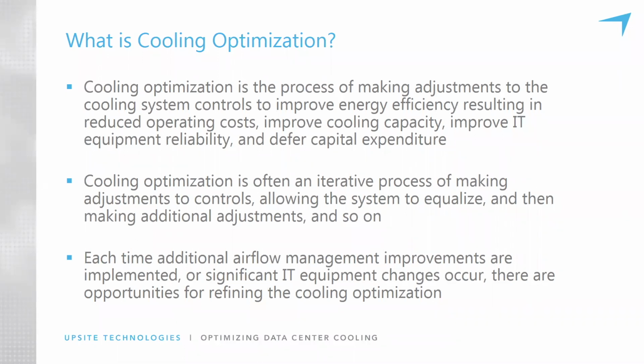There are many business cases where improved airflow management prevented the construction of either a new data center or a substantial remodel addition to an existing data center. And the value of the savings of deferring those massive capital expenditures can be enormous. Or even if it just means deferring the capital expenditure for buying another cooling unit. Most data centers have way more capacity than they need. It's just a question of utilizing that capacity that's already been installed more appropriately.